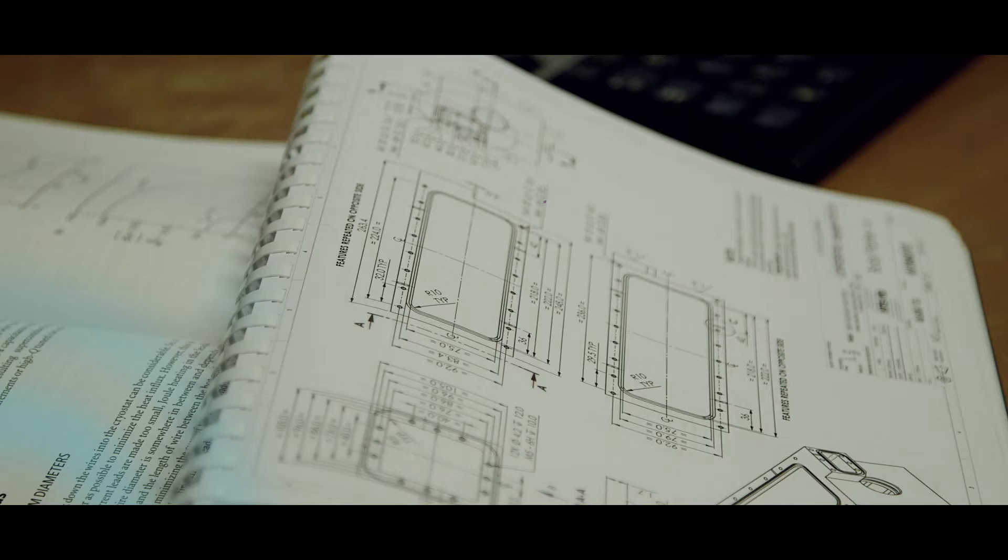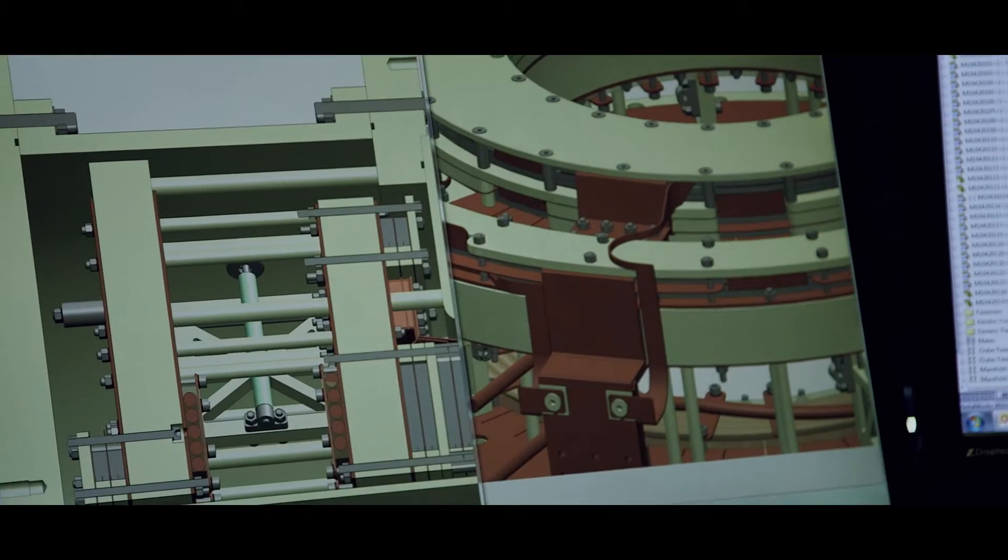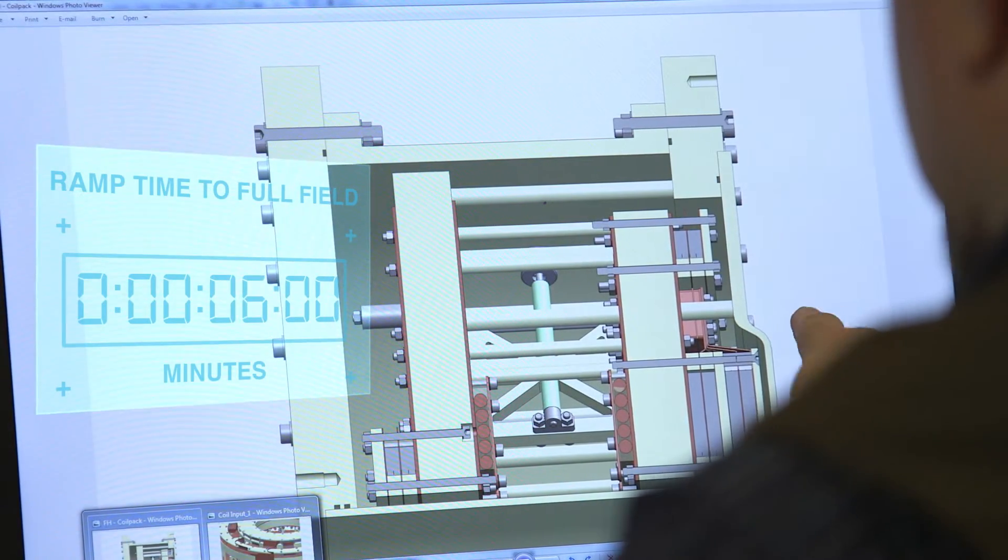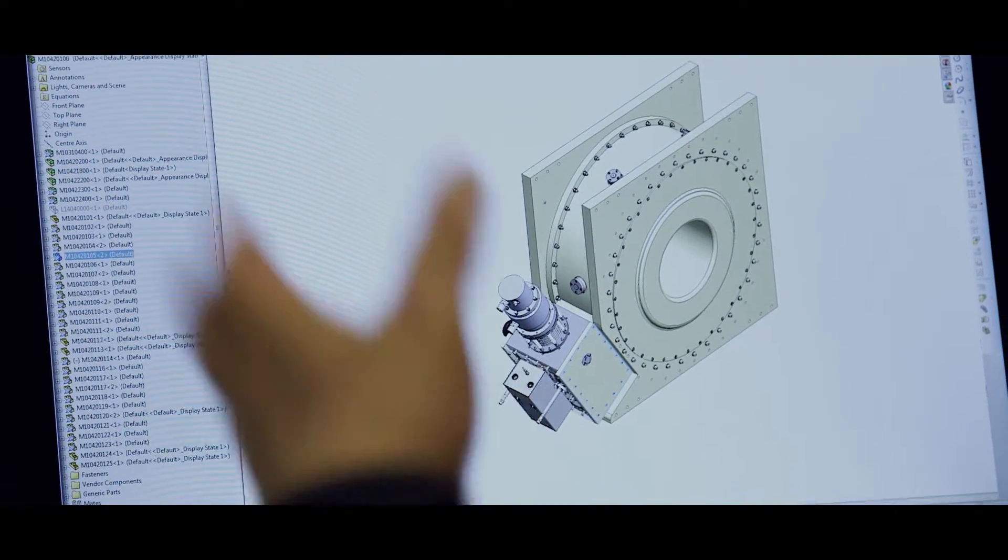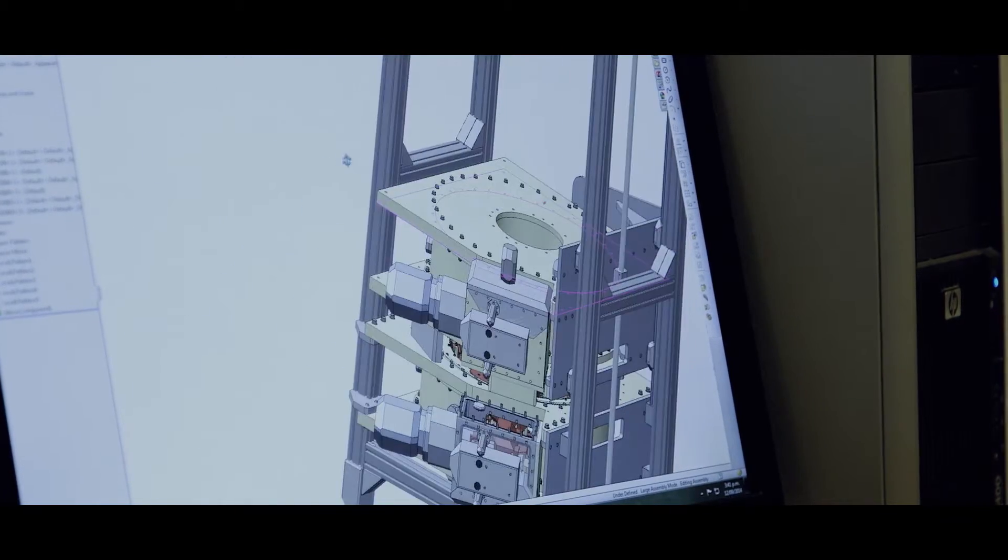In this particular project we made some challenges during the embodiment design. To meet requirements of the magnetic design, we have to extensively use composite materials considerably larger than in any other magnet previously designed by HTS-110. The interlacing support of the coil assemblies is complicating in its support coils inside, and we use vacuum inside the magnet to counteract magnetic forces. The support of the coils inside the magnet is designed the way that this magnet can work in either vertical or horizontal conditions.